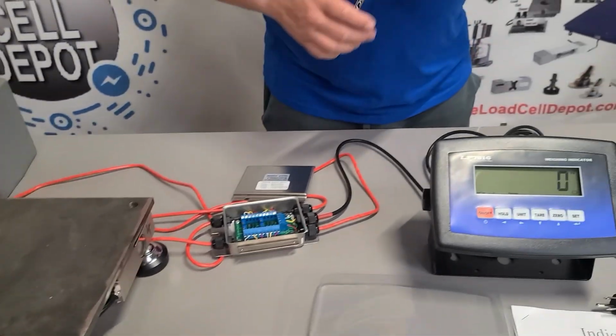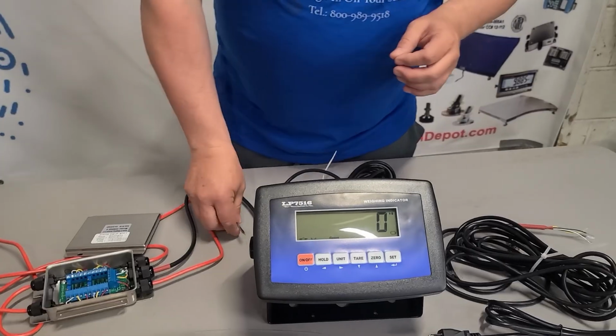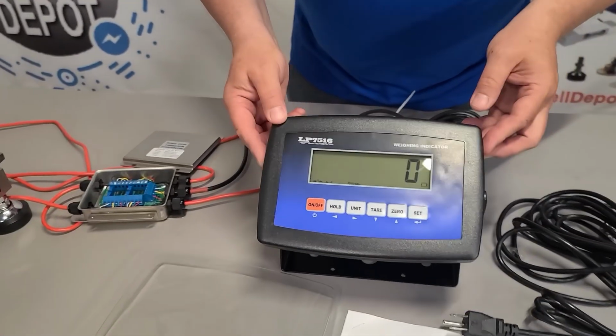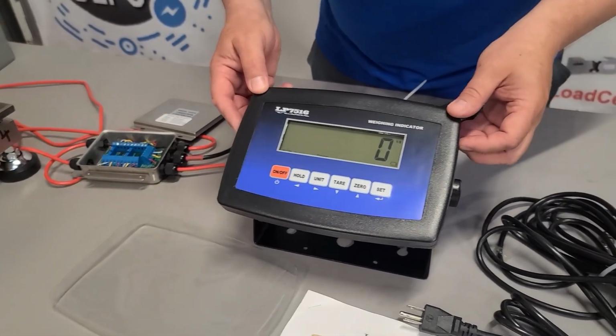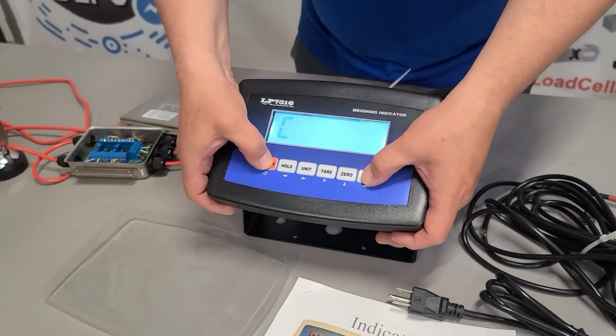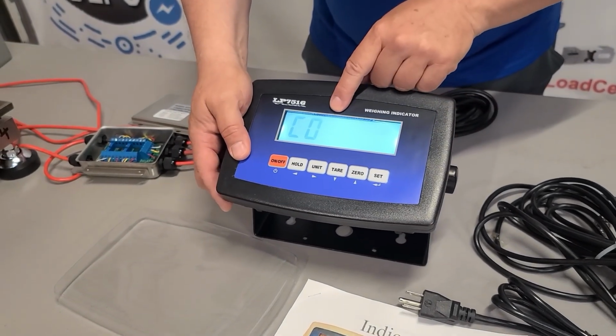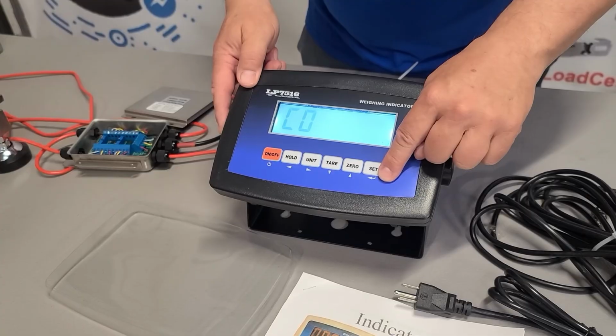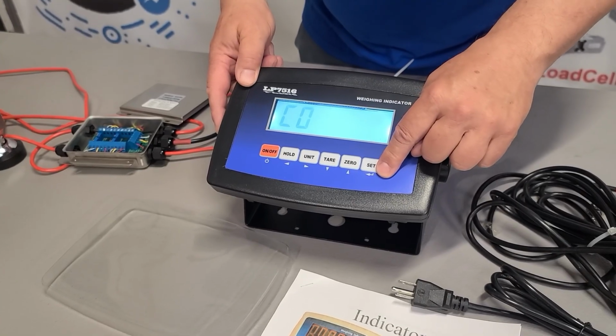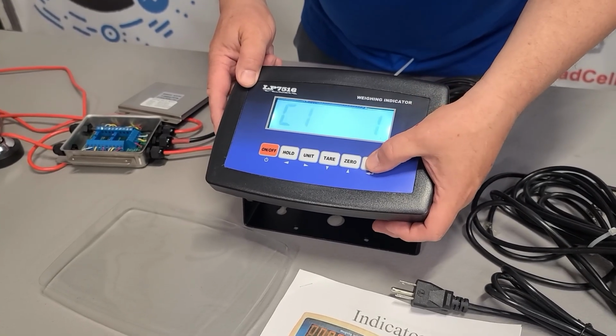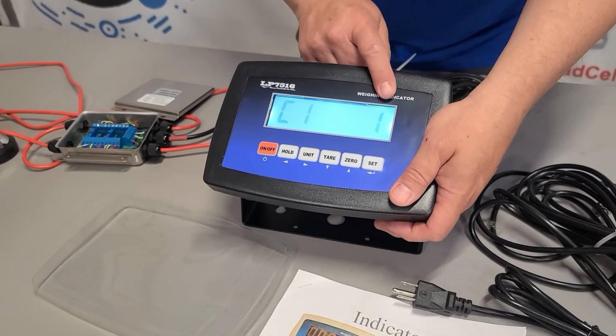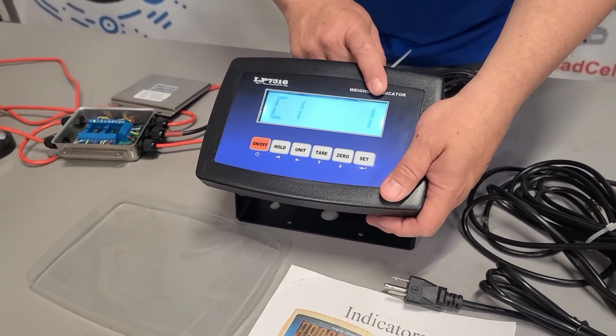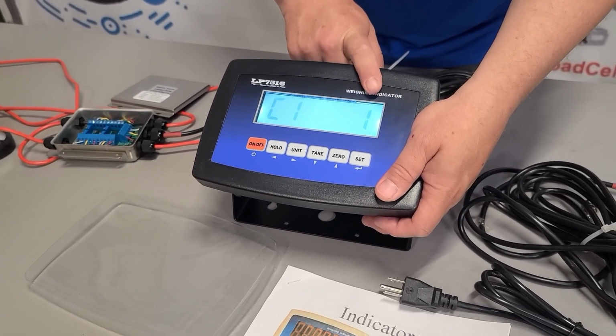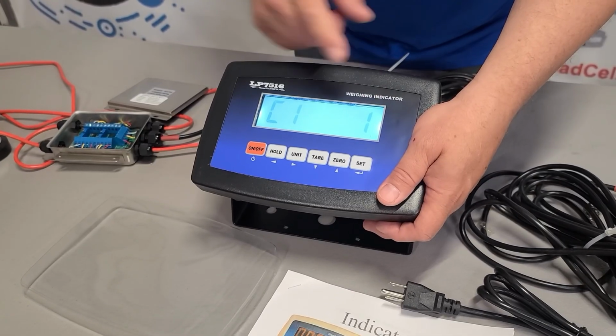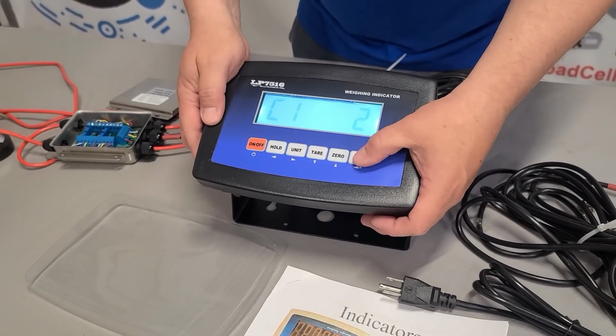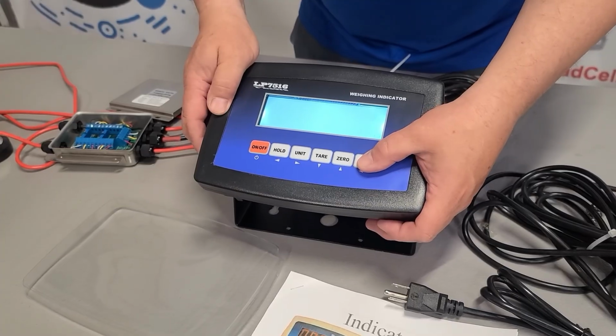What we can do is calibrate that particular indicator. To calibrate this indicator, you have to press 2 buttons, the on and off and a set. It's going to show you C01. The set button is obviously the enter button because these are double function buttons. C1 is going to stand for weight calibration of pounds or kg. Kg is number 1, pound is number 2. So we take the 2 because we're going to use a pound test weight.